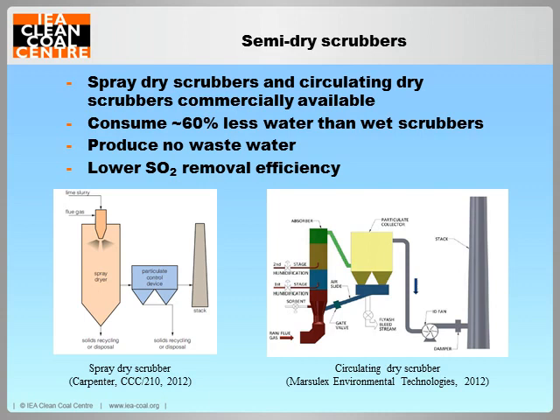However, their sulfur dioxide removal efficiency is lower. It's some 90 to 97% for spray dry scrubbers and just over 98% for the state-of-the-art circulating dry scrubbers. The removal efficiency for wet scrubbers is nearly 99%. However, semi-dry scrubbers can capture more sulfur trioxide and oxidised mercury than wet scrubbers.